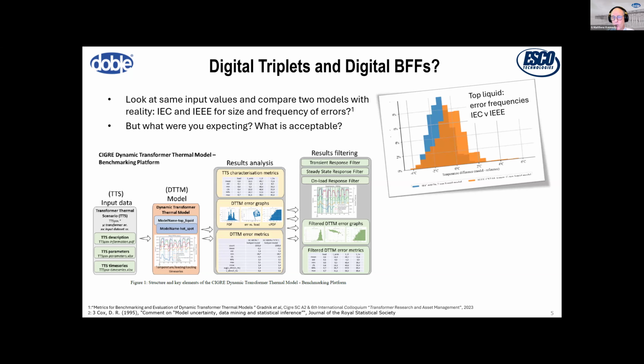Both IEEE and IEC have developed standards that discuss this - IEEE C57.91 and IEC 60076. This tells you a prediction of the model for how much that temperature could vary based upon the temperature differential. Looking at this, IEEE might be a little more truthful, more centered around that 0-degree change, than IEC, which runs a little low.